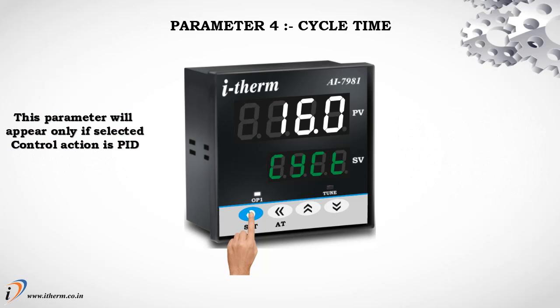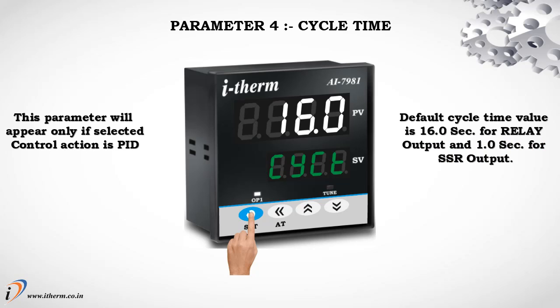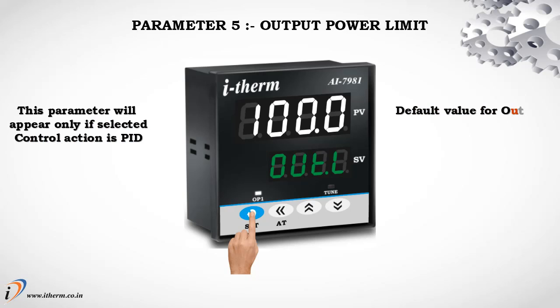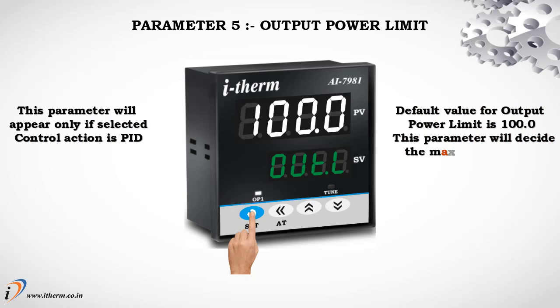Parameter 4: Cycle Time. This parameter will appear only if selected control action is PID. Default cycle time value is 16.0 seconds for relay output and 1.0 second for SSR output. Parameter 5: Output Power Limit. This parameter will appear only if selected control action is PID. Default value for output power limit is 100.0. This parameter will decide the maximum output power in percent applied to the load.